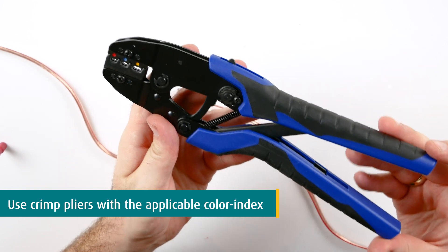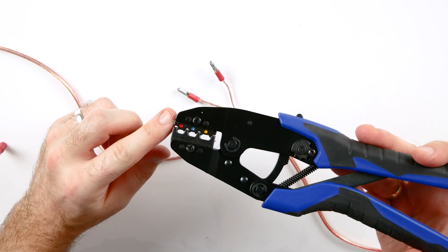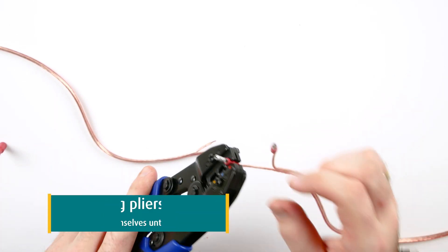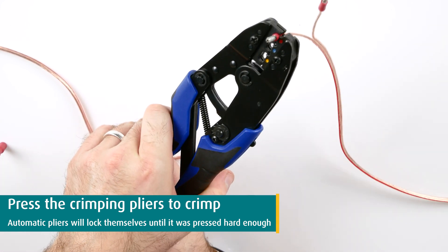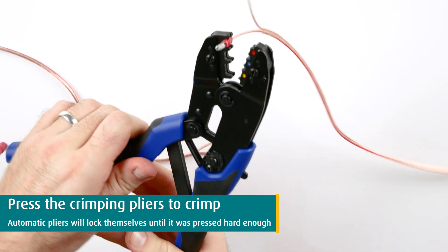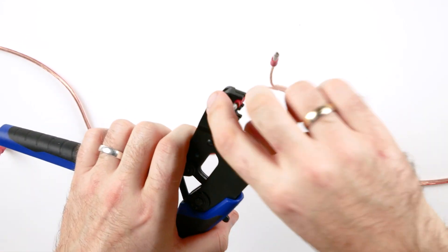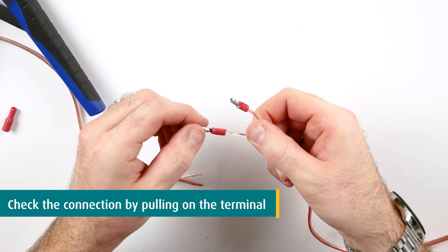Use the correct color index profile of the crimp pliers and press it firmly. If you use an automatic plier like this one, it will lock itself until you have applied sufficient force. When crimped, check the connection by pulling on the terminal to make sure that it sits tightly and doesn't come off.